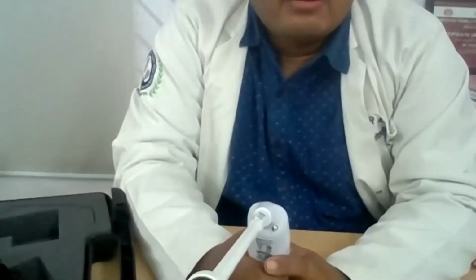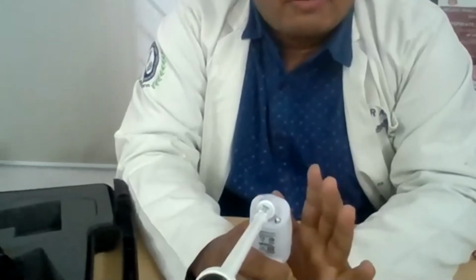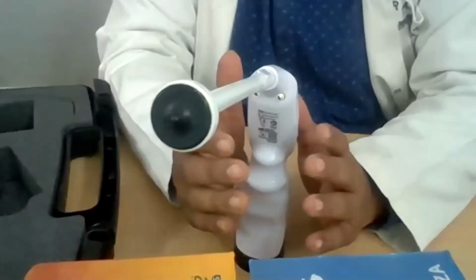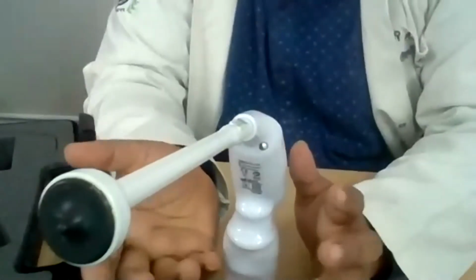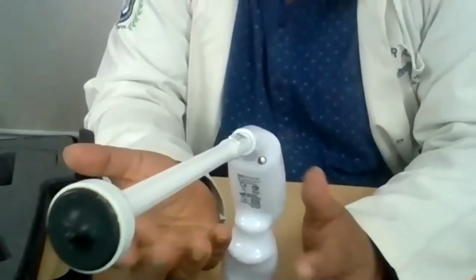That is what my question is. If I am doing a big hypertrophied cervix, then I would go for the first throw, and it is coagulated, right? And then the light will still remain on. So I may be in a hurry, and then I'll do it again. No, you have to pull it out of the vagina, and you will have to give 8 seconds. It takes only 8 seconds. It goes off, and then you are ready for the second throw. So once in, we cannot do it the entire thing together. I will tell you, it is almost like doing it together only. It takes hardly, by the time you are adjusting your probe, it goes off. By the time you are taking the instrument out of the speculum, the light will go off. So it is hardly 8 seconds. Okay. It's a very short duration.